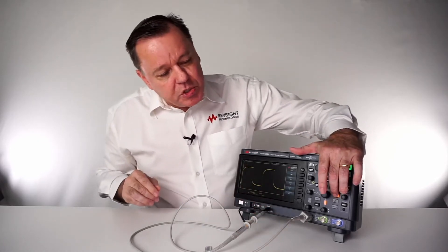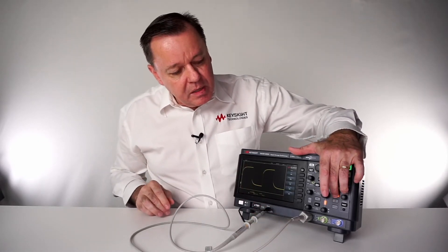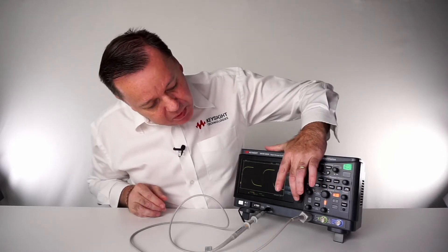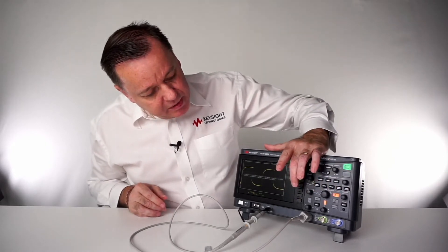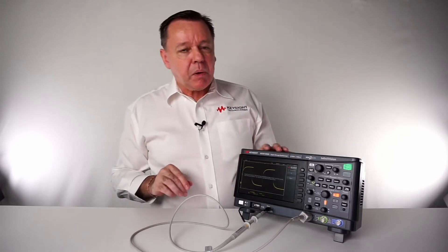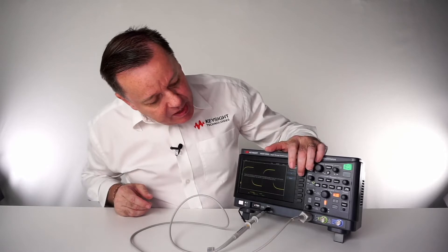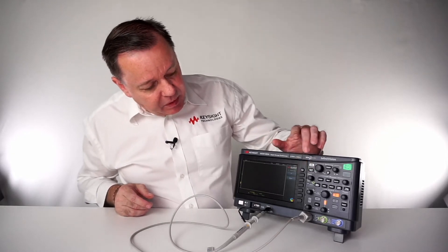Then we push on the channel that we want to adjust, select probe, probe check. Now the display shows that we have to connect it. We've done that already, and I say okay, now let's check.